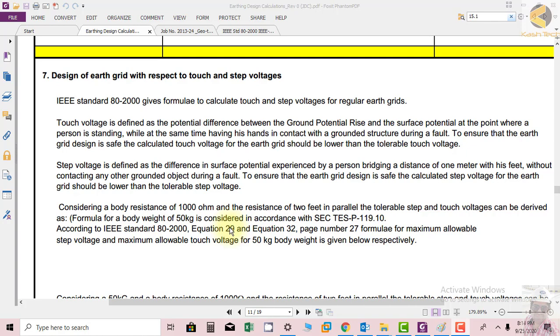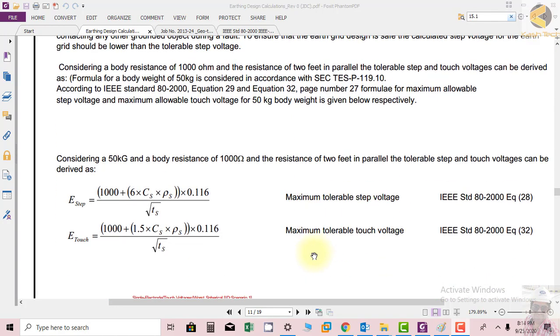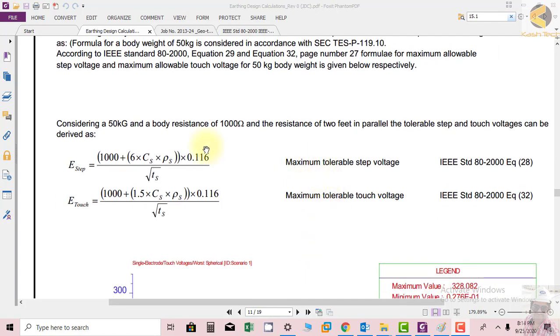Considering a body resistance of 1000 ohms and resistance of two feet in parallel, the tolerable step and touch potentials can be derived. For a body weight of 50 kg, according to IEEE standard 80-2000 equation 29 and equation 32 page 27, the formulas for maximum allowable step voltage and maximum allowable touch voltage for 50 kg body weight are given below respectively.